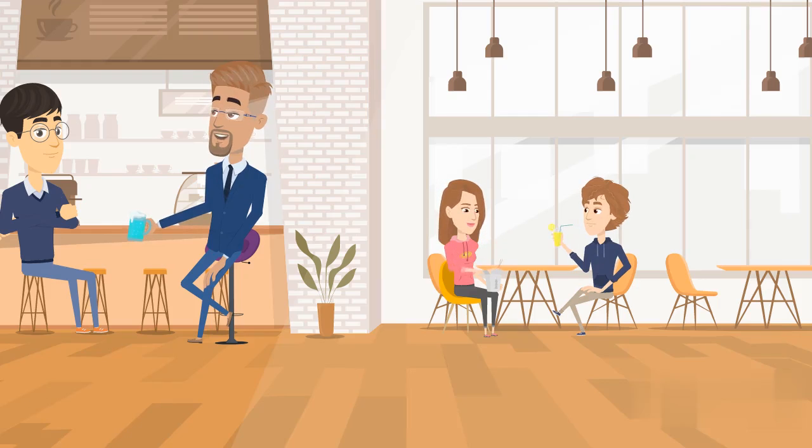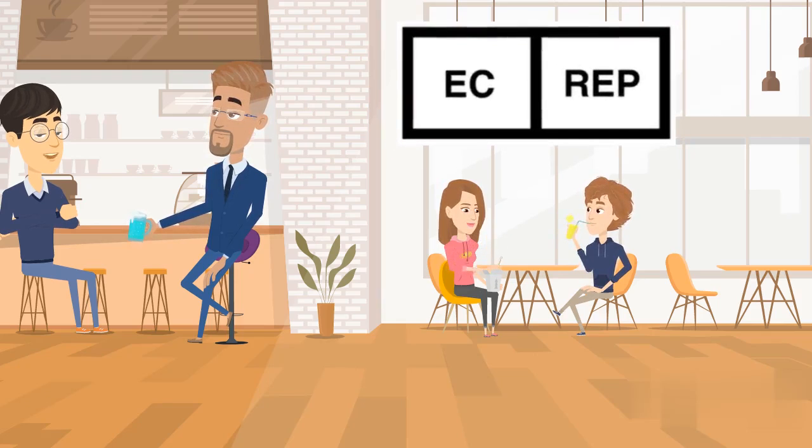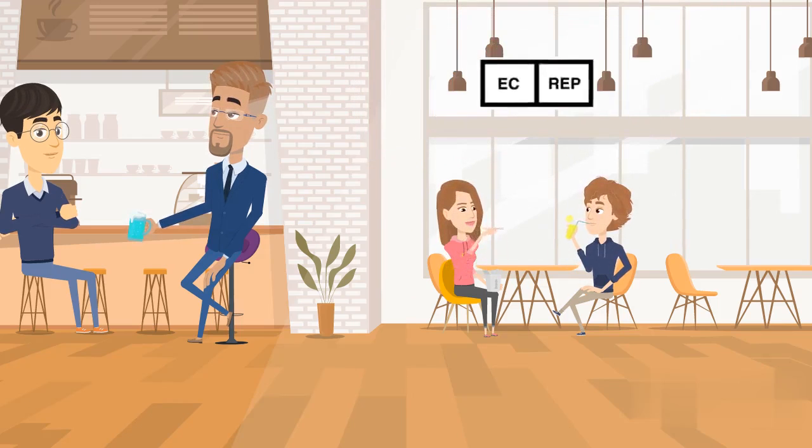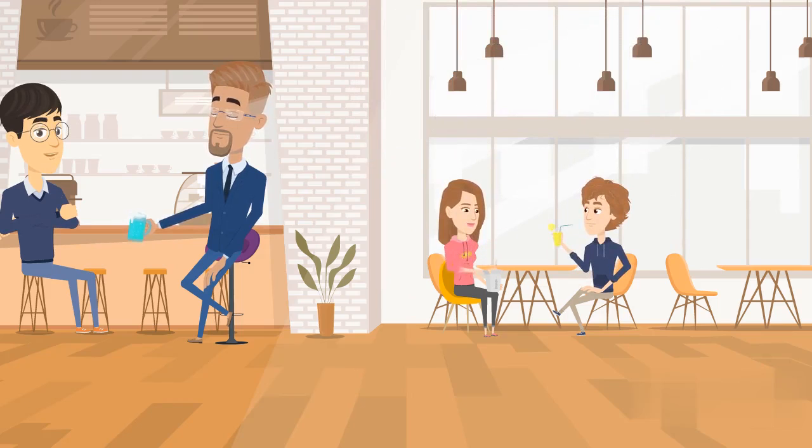Do the authorized representative details appear on the product? Yes, you must list the name and address of the authorized rep on the product label, outer packaging, and/or instructions for use. The name and address of the authorized representative should be shown next to the official EC rep logo. One important risk of having your authorized representative detail on your product is that when you want to change him, it can cost you an arm and a leg. Because you'll have to change all your labeling, packaging and instructions for use, tell the competent authorities and your notified body, and change the marketing material.